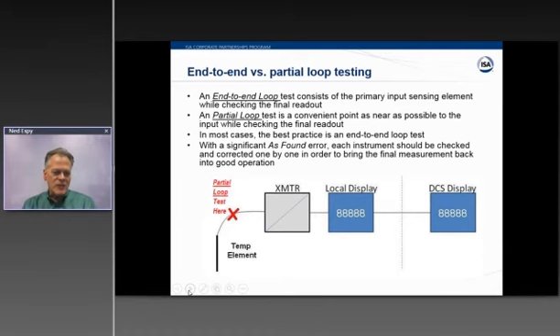So here we are disconnecting the temperature element for the partial loop test. We would shoot either ohms or millivolts into the transmitter and compare that to the DCS. And if you do have to make a partial loop test, it would be best practice if you could also do some kind of single point check on the temperature element that's in the process.